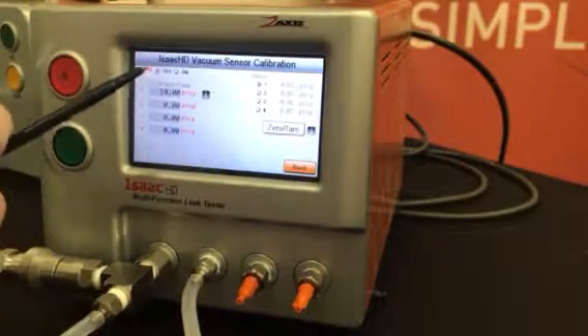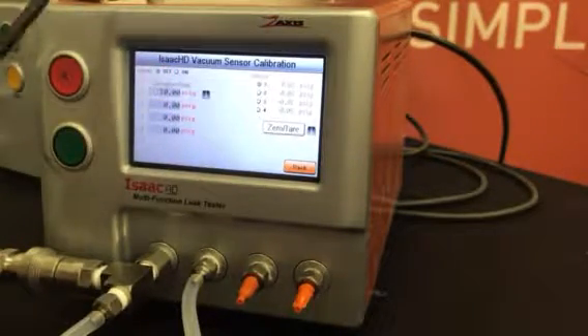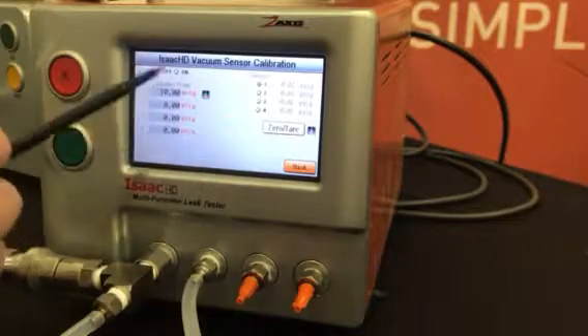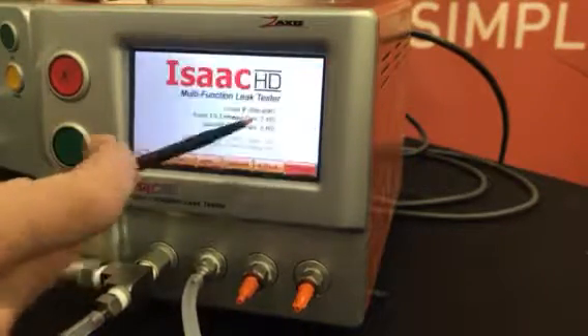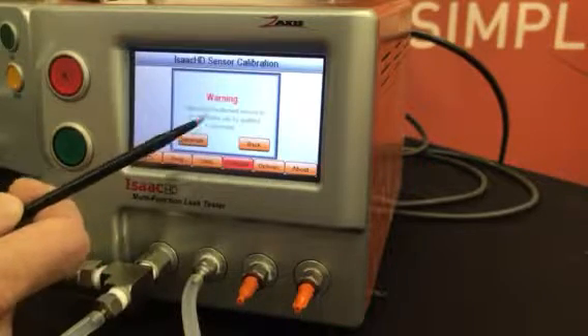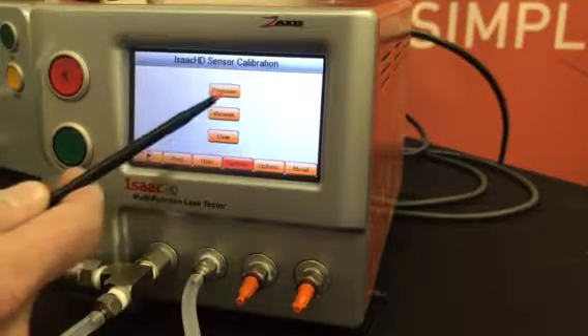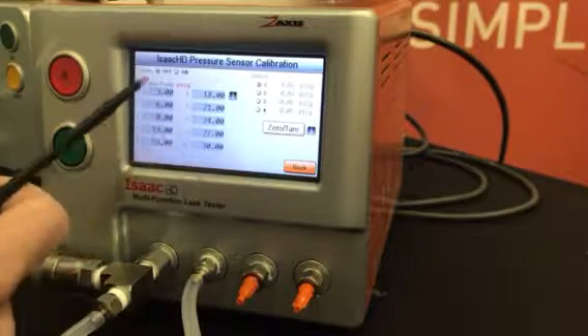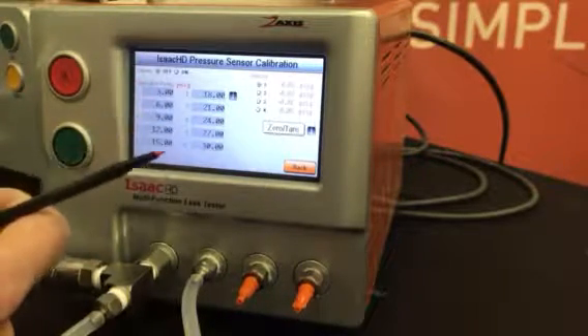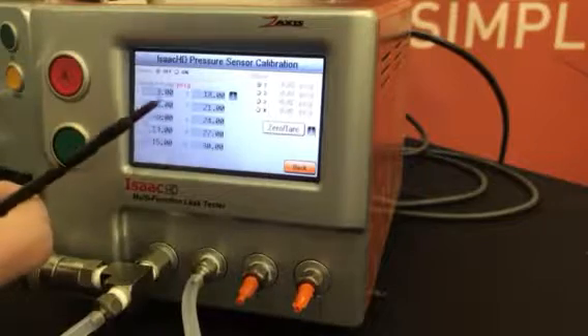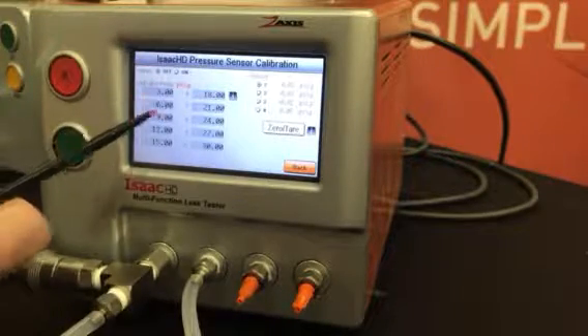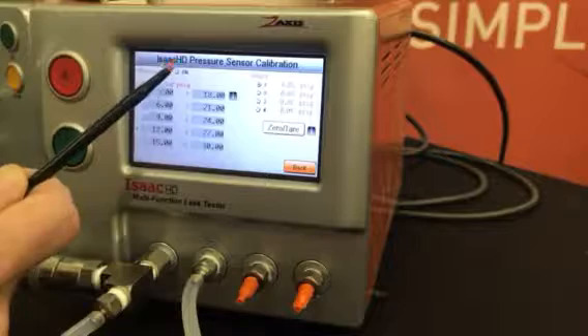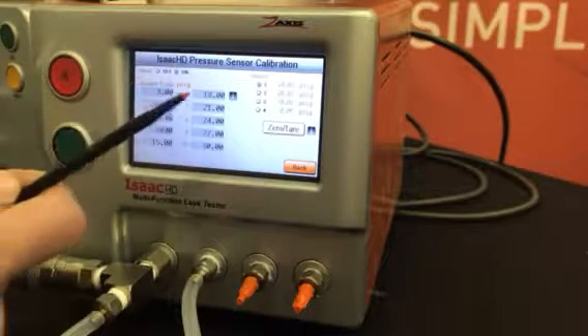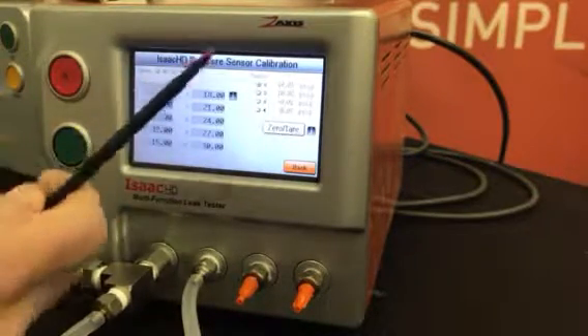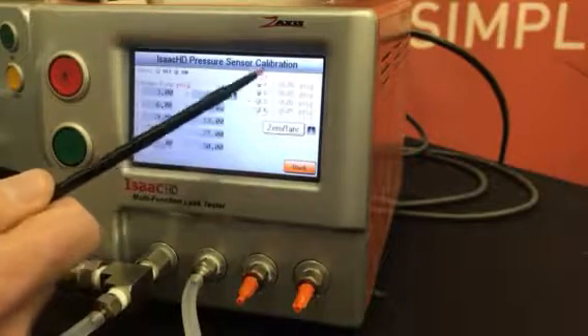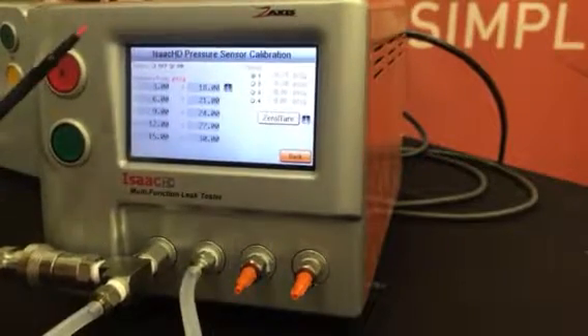So I'll actually go through the numbers on here on the positive side. This tester right here does not have vacuum, so I didn't want to touch any of these actual cal points. So I'm going to go back into cal, go to the pressure side, and see this is a 0 to 30 tester. Yours, I believe, is 0 to 10 or 15, I think. But see, mine has 3 through 30. So doing the same thing, I'm going to go valve on. So now the pressure is coming through. Mine are 1 and 2 hooked up. It says 10 PSI. So I'm going to adjust the regulator.